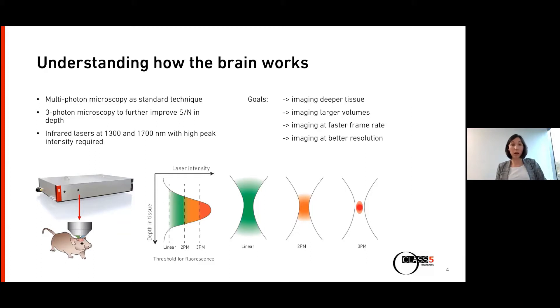Most of the audience are familiar with multiphoton microscopy, so we'll briefly address the advantages. Today we speak about three-photon microscopy, which is the improvement over two-photon microscopy. For three-photon microscopy, you work with infrared lasers — for example, 1,300 nanometer for green fluorescence proteins and 1,700 nanometer for red fluorescence proteins — and you need quite high peak intensity, meaning high pulse energy and short pulses.